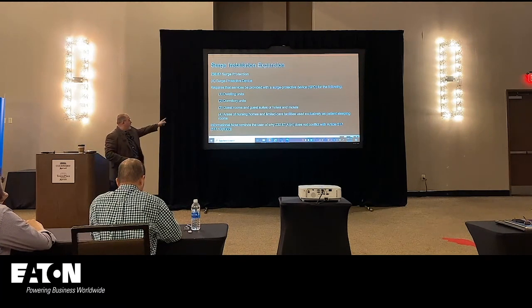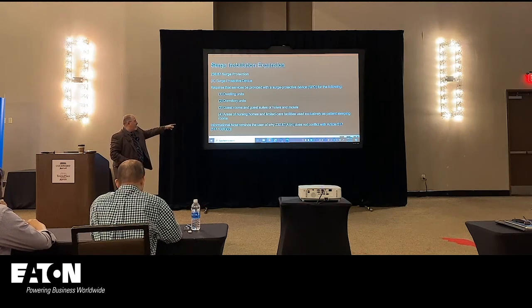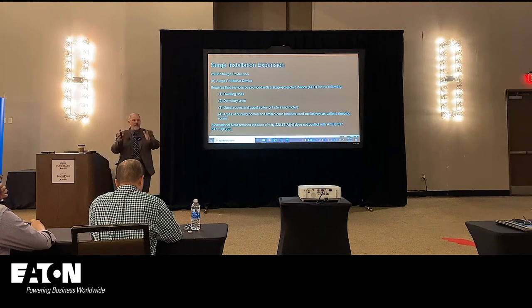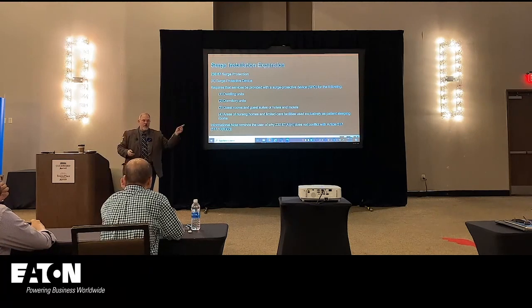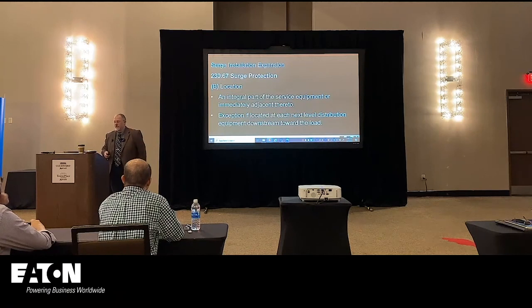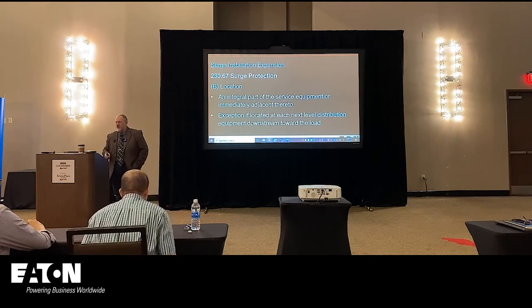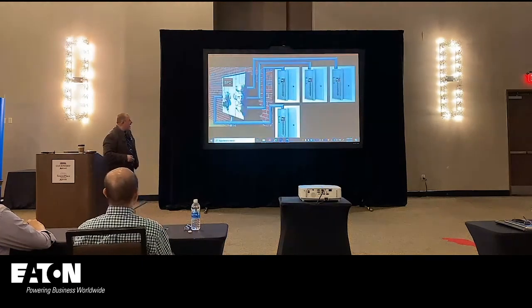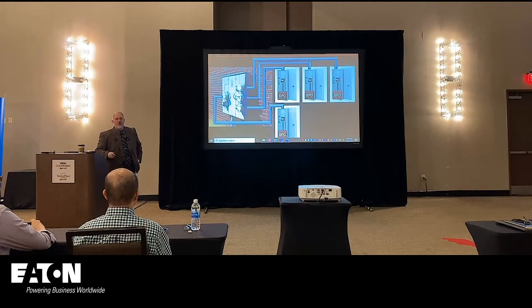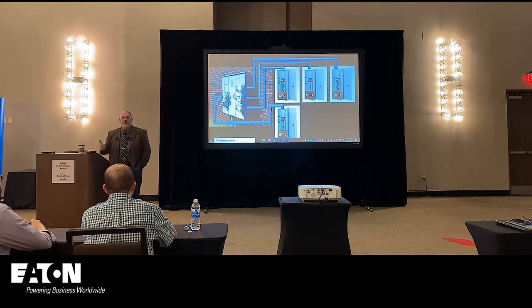So, dwelling units, there are the four areas that we added. And then this was in 230, so we said if you have it at the location, at the structure, in 215 or 225, then you don't need to put it in 230.67. We want it to be an integral part of the service equipment or immediately adjacent thereto. And there's the exception if it's located at the next level of distribution. So basically I could put surge there in an application, or if I put it at all the next level distribution, then I don't need it there, right? And that's good for your multi-family dwelling units and your larger installations.